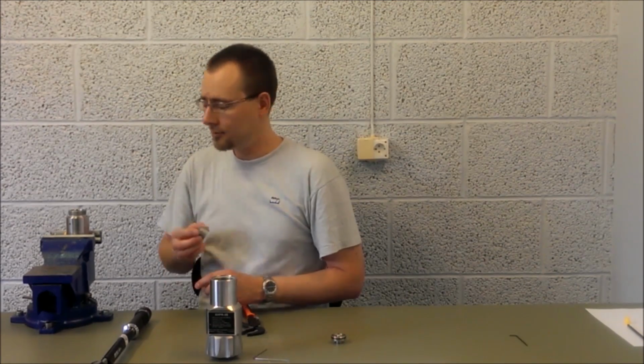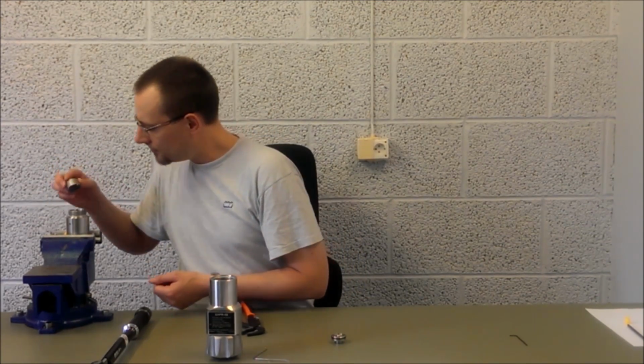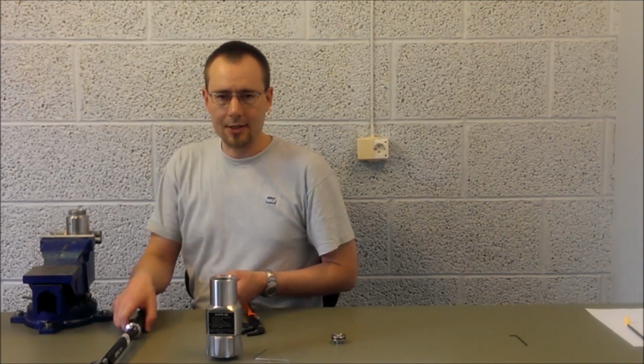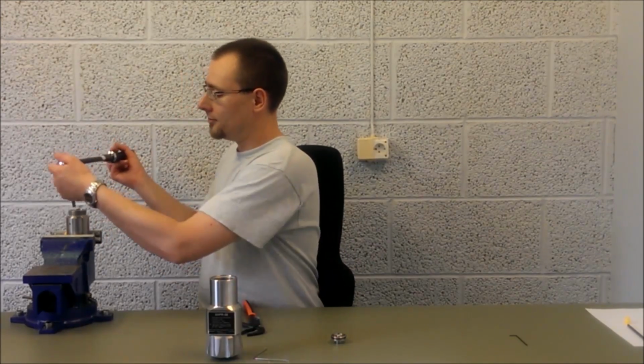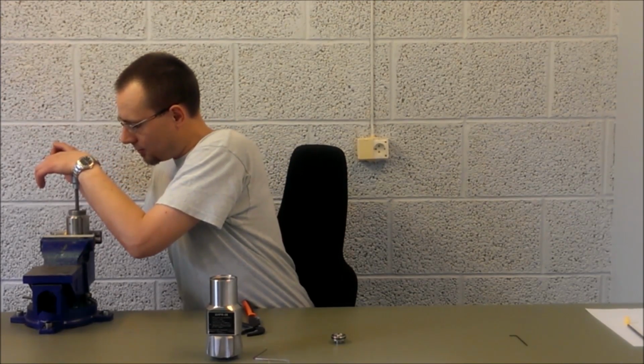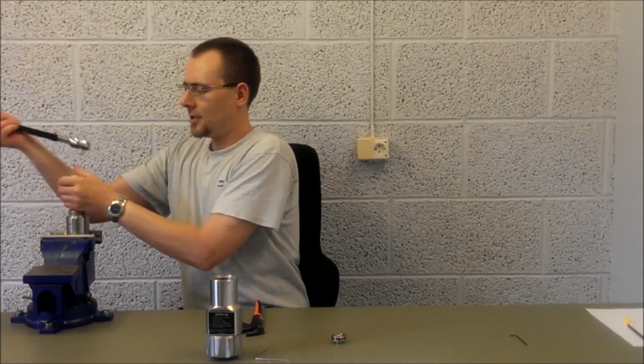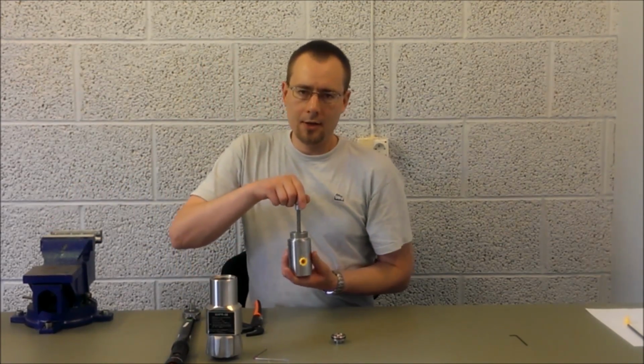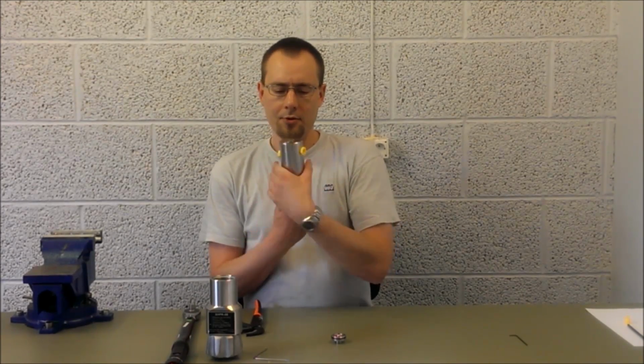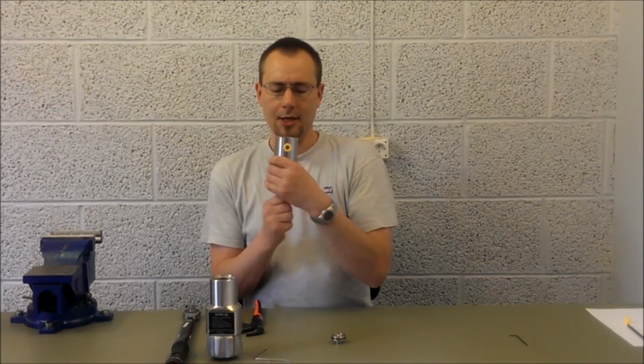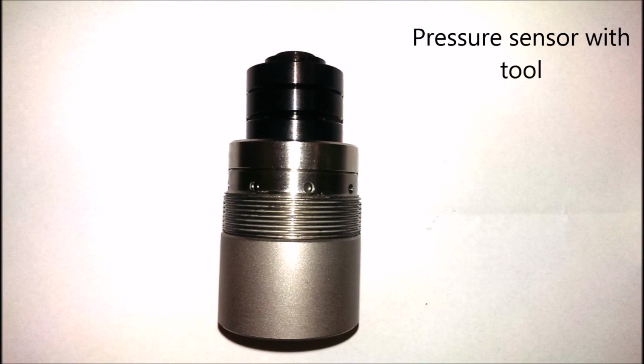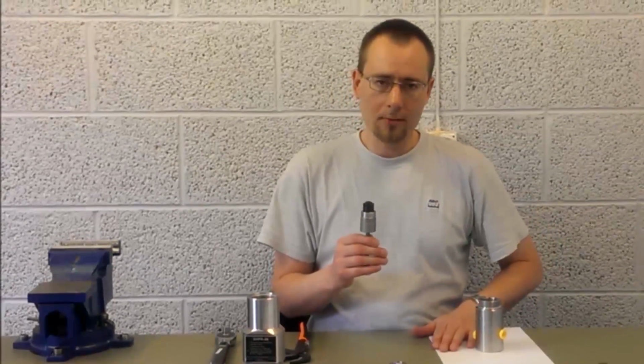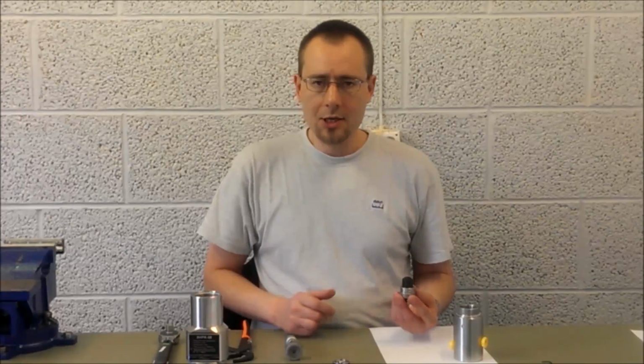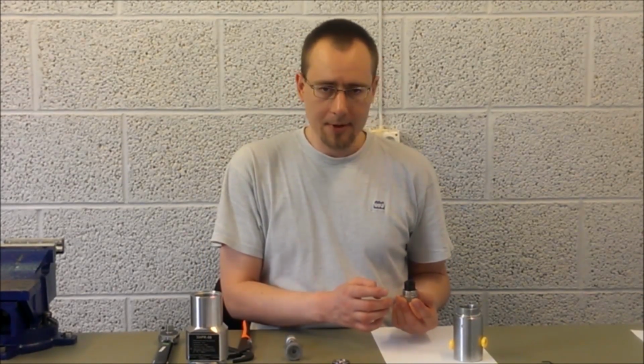Take the special dump tool and find the holes in which it fits. To unscrew, apply pressure down and turn counterclockwise. Now it's loose. Turn it upside down and screw the pressure sensor out of the housing. Off, and then you have the whole pressure sensor with a dump valve. For changing of the dump valve, you have to separate the parts of the pressure sensor.